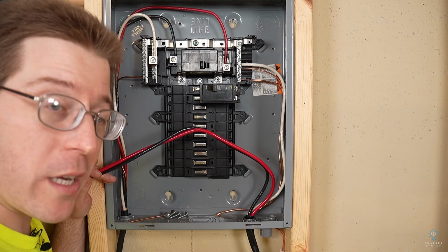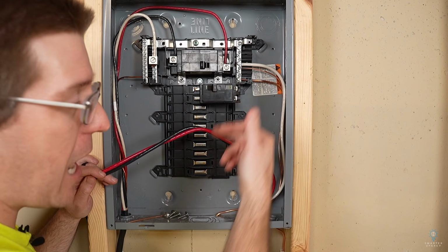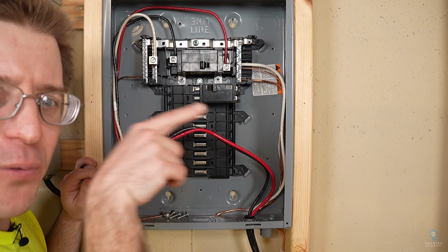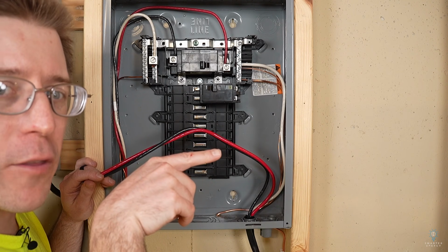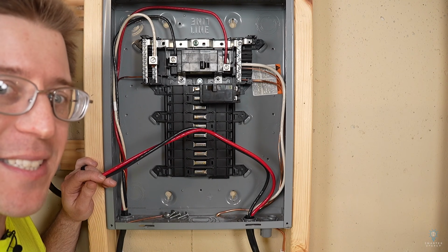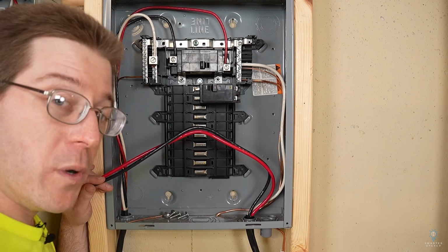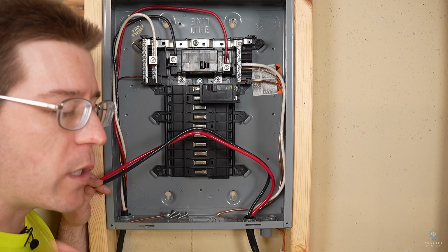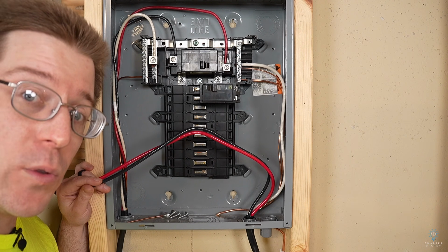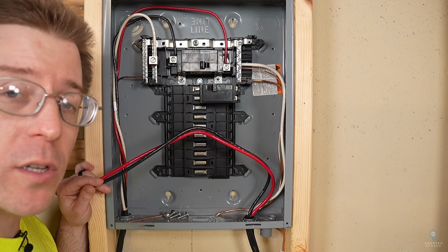Would it work if we flipped them around and we had red on top and black on the bottom? Yes, but your phasing is gonna be a little bit different on your other panel. But for a single phase system, that really doesn't matter. When you start getting into 3-phase systems, you really wanna make sure your phasing is consistent throughout the building. That way all your motors spin the correct direction.